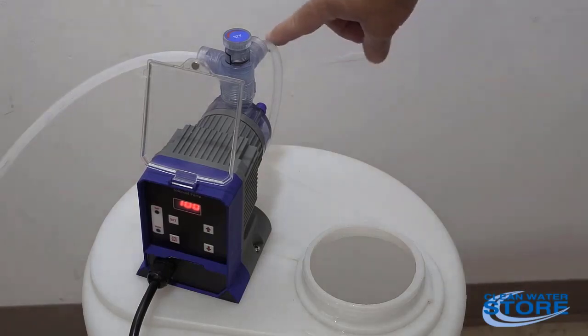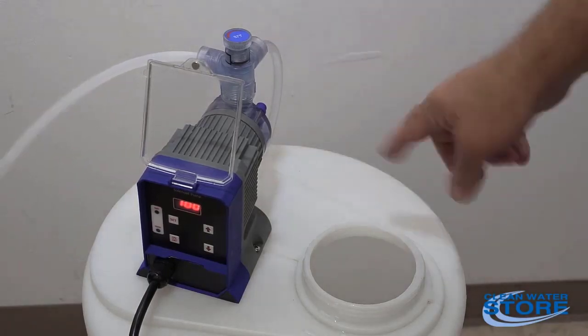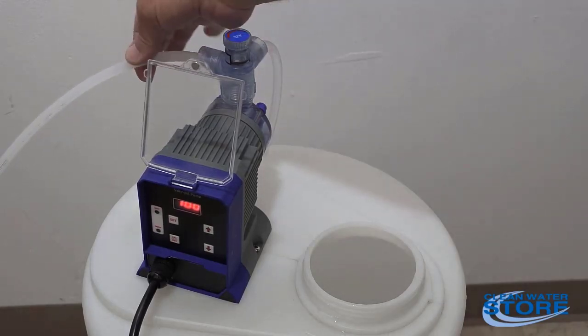You can see there's no more air bubbles in here. You've got just a little dribble of water coming out this hose. This guy's kind of shaking a little violently there. That's a good sign. That means you're primed.